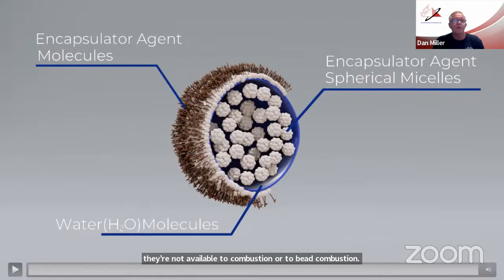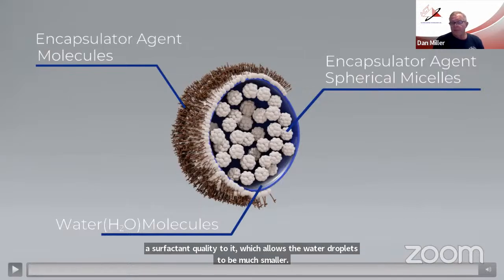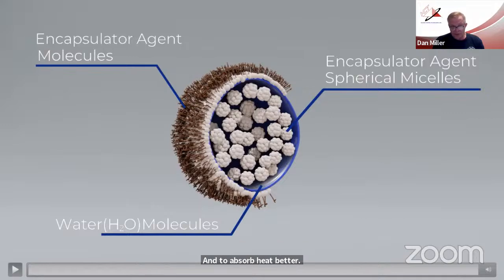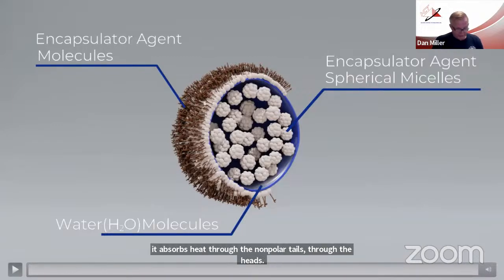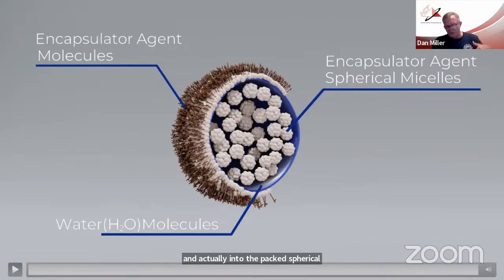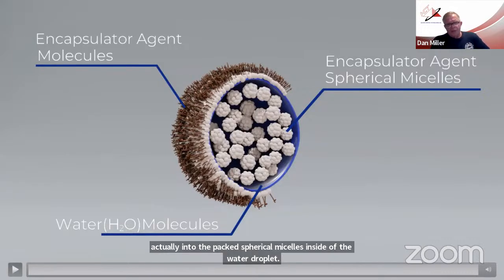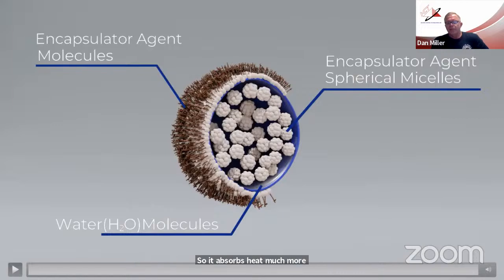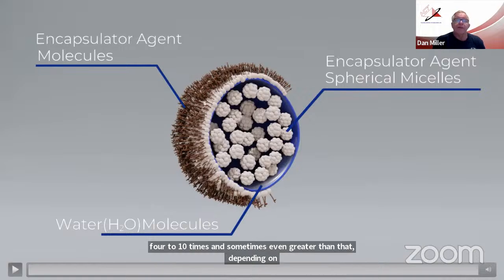Since they're trapped inside the water droplet, they're not available to oxidize or feed combustion. It also has a surfactant quality, allowing the water droplets to be much smaller and absorb heat better, through the nonpolar tails, the heads, and into the packed spherical micelles inside the droplet. It absorbs heat 4 to 10 times more efficiently than a plain water droplet, sometimes even greater, depending on the fuel package.